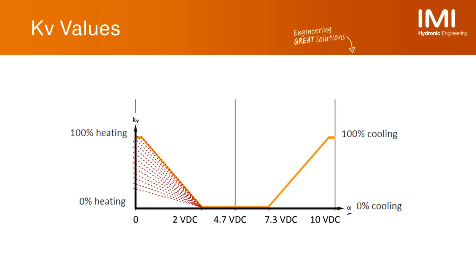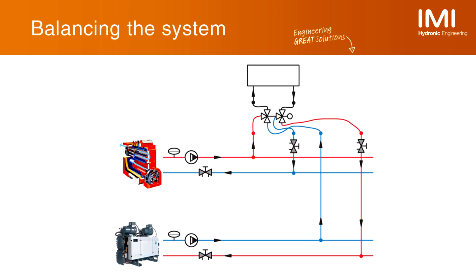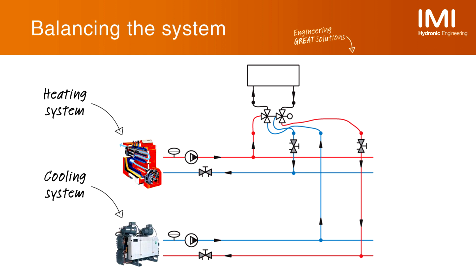Another issue is that different KV values are needed for the heating and the cooling port of the six-way valve, requiring as many as 25 different versions for each dimension of the six-way valve. Additionally, in order to provide the right flow in heating and cooling, balancing needs to be achieved both in the hydronic heating network and the hydronic cooling network.